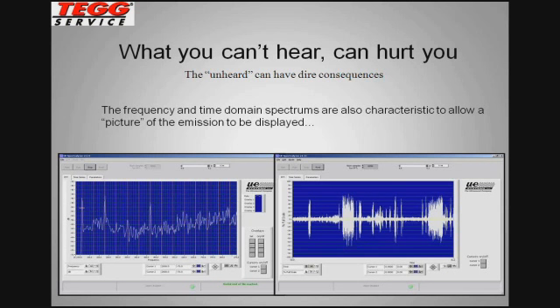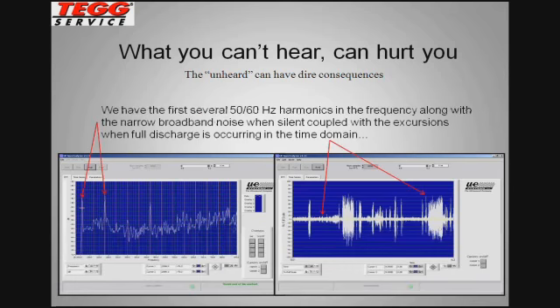And the next slide kind of explains what I said, because I'm very bad at switching slides, so I'll have to apologize. But the first couple of harmonics in the frequency, a lot of frequency content in between those harmonics, and then the excursions do not have a distinguishable pattern across the time domain, but you can see and visualize the discharges, back to full silence, and when the discharge occurs once again.